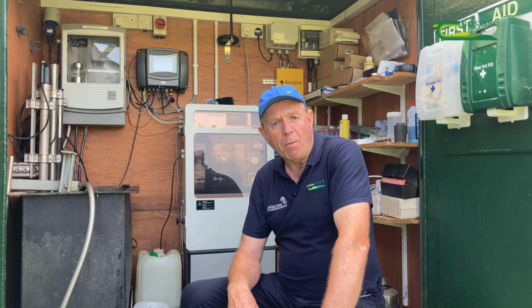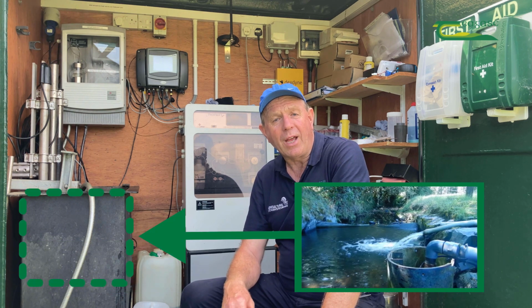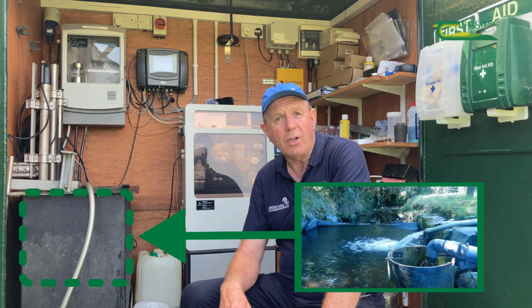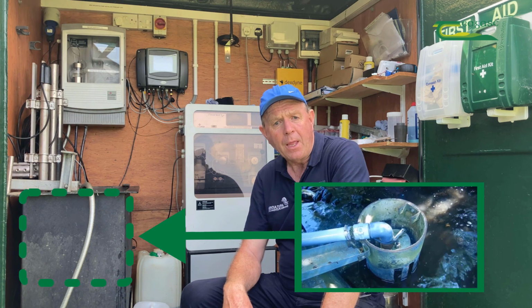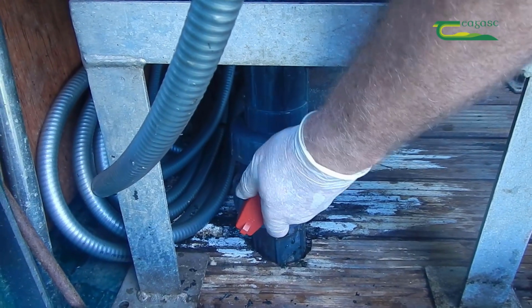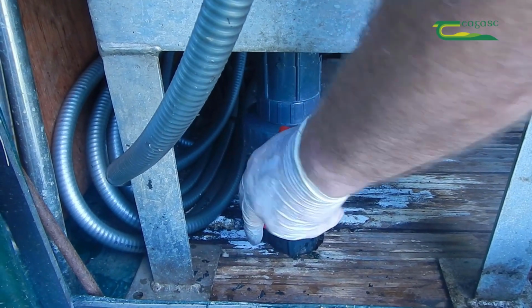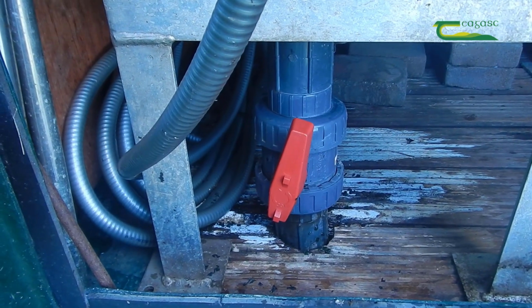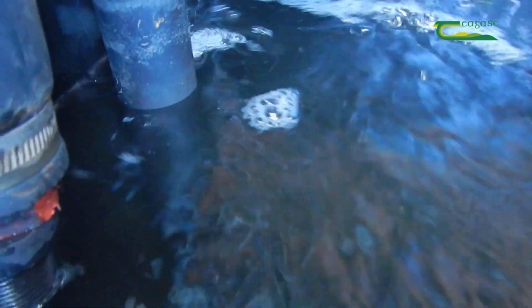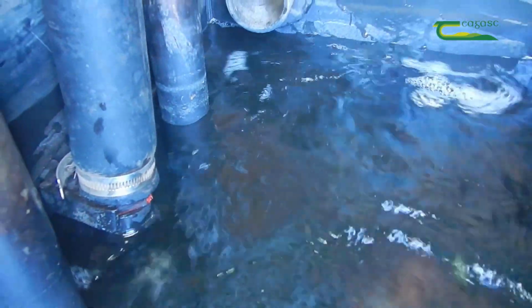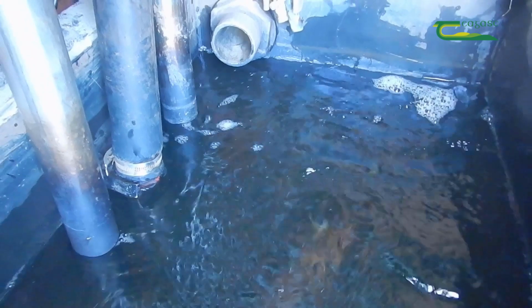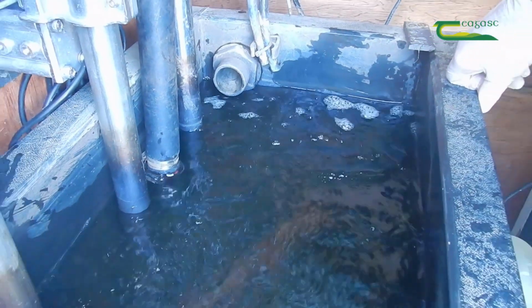We have a pump in the stream here behind the kiosk, and that pump is pumping water into a header tank in the kiosk 24/7 every day of the year. So there's an inlet valve and an outlet valve into the header tank. So the water in the tank is representative of what's in the stream at any given time. Within this tank in the kiosk then contains our various probes and equipment that measure and monitor the water.